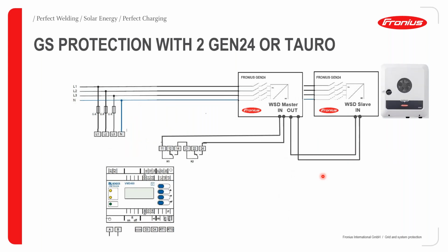Now in a case where you have only Gen 24 inverters or Tauros, you don't need a buffer. All you need to do is connect directly to the WSD terminals and loop it serially. Of course, you would have a master, and then the others would become slaves. We'll be seeing how we can have one as a master and the subsequent ones as slaves in the next slide.